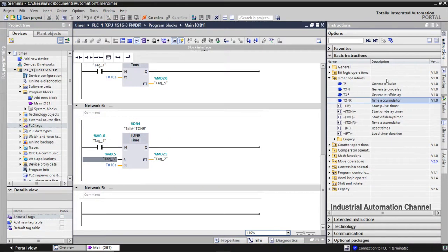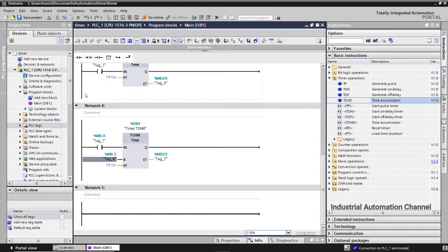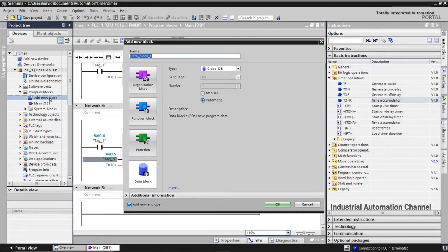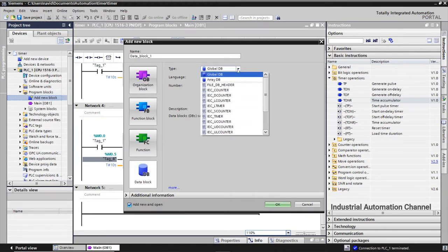Let's talk about these instructions. Here you can find again the timers in TIA Portal in form of a coil. There is a little bit of difference between coil type and block type. If you use coil type you need to define a data block manually. To do that, double click on add new block and select data block. Open data block type and select IEC timer.